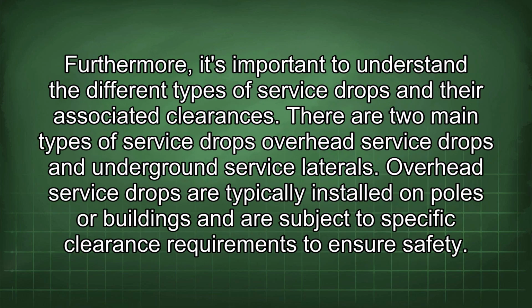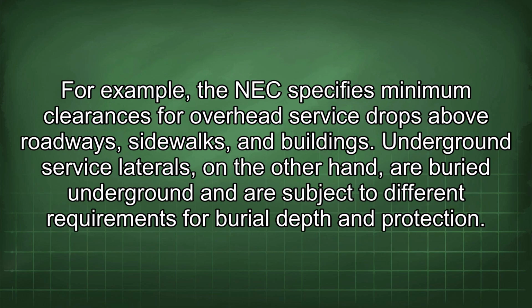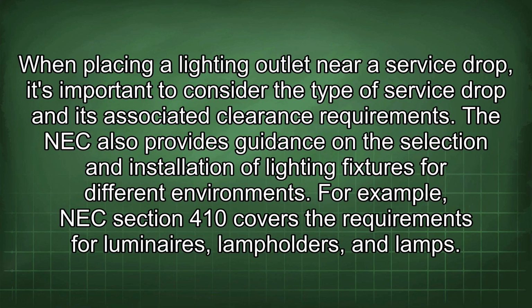Furthermore, it's important to understand the different types of service drops and their associated clearances. There are two main types of service drops: overhead service drops and underground service laterals. Overhead service drops are typically installed on poles or buildings and are subject to specific clearance requirements to ensure safety. For example, the NEC specifies minimum clearances for overhead service drops above roadways, sidewalks, and buildings. Underground service laterals, on the other hand, are buried underground and are subject to different requirements for burial depth and protection.